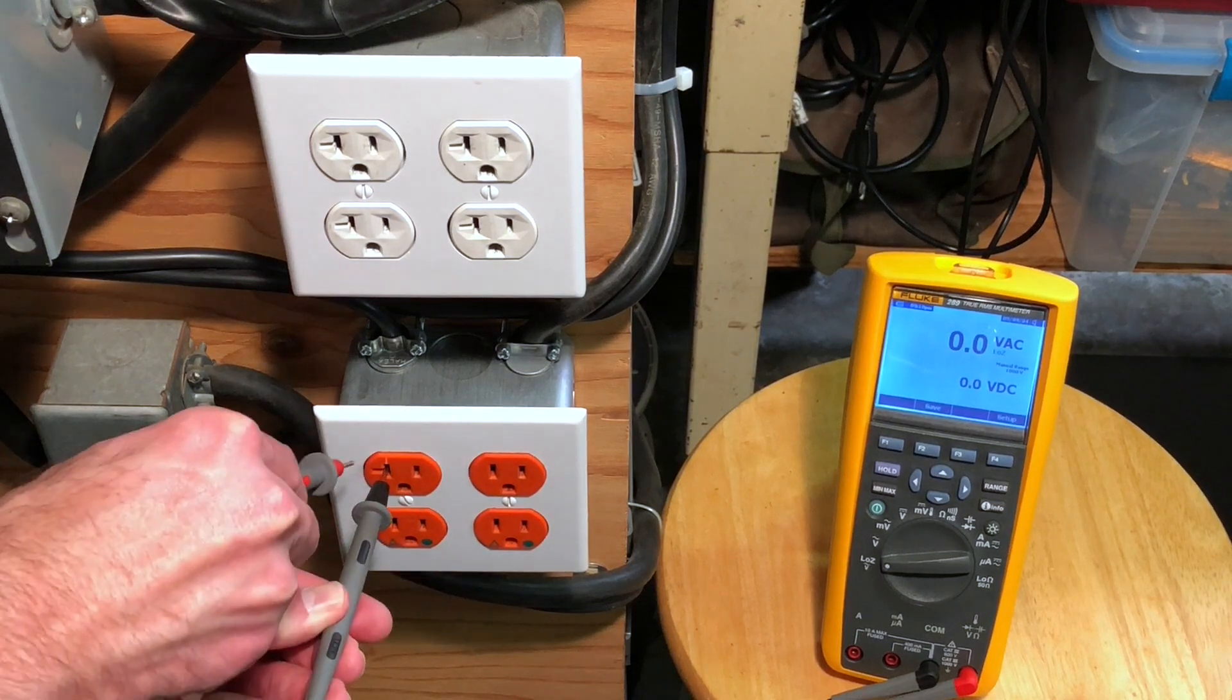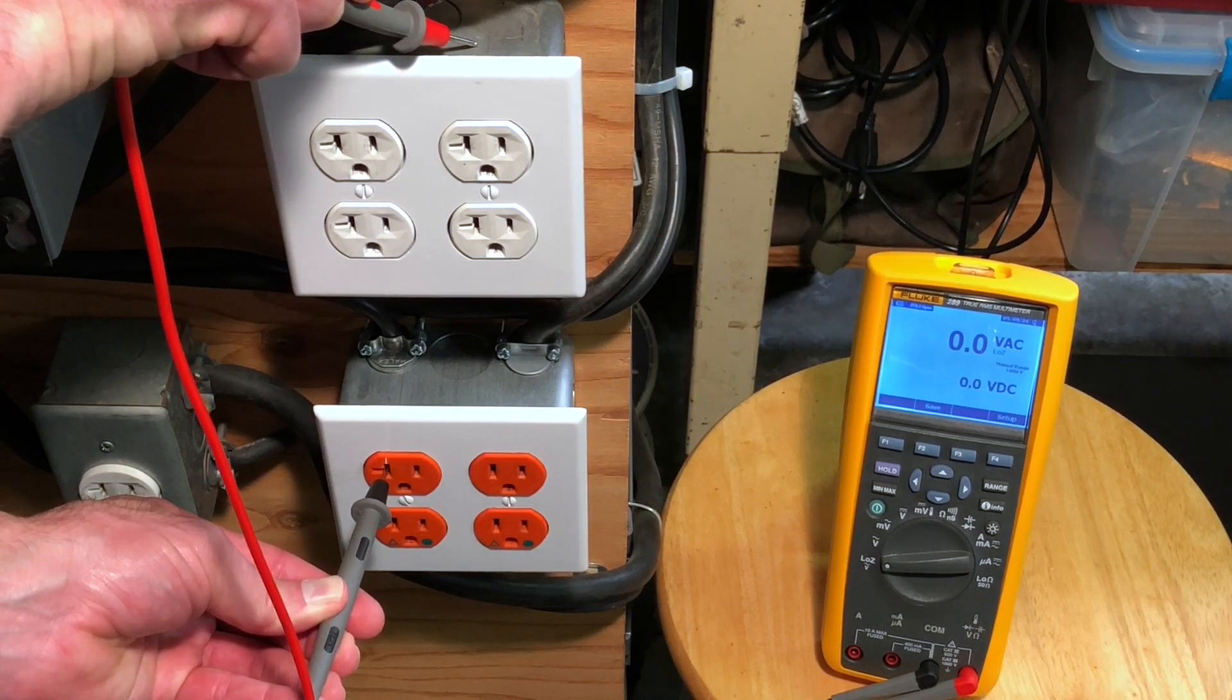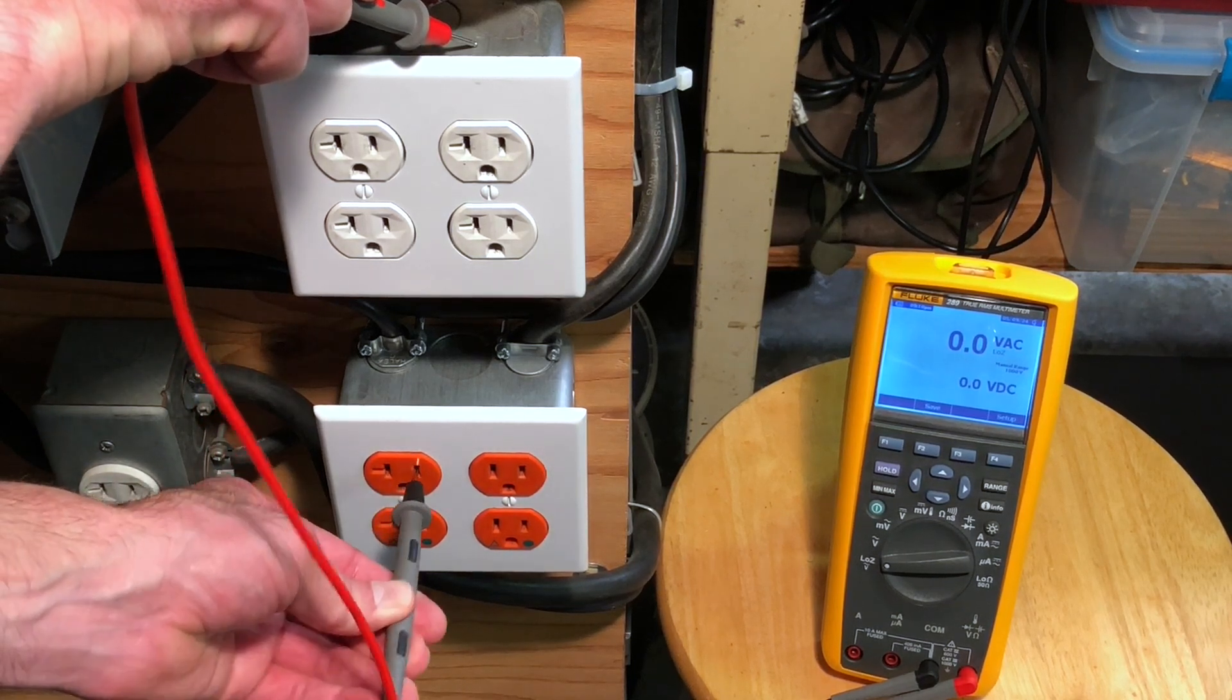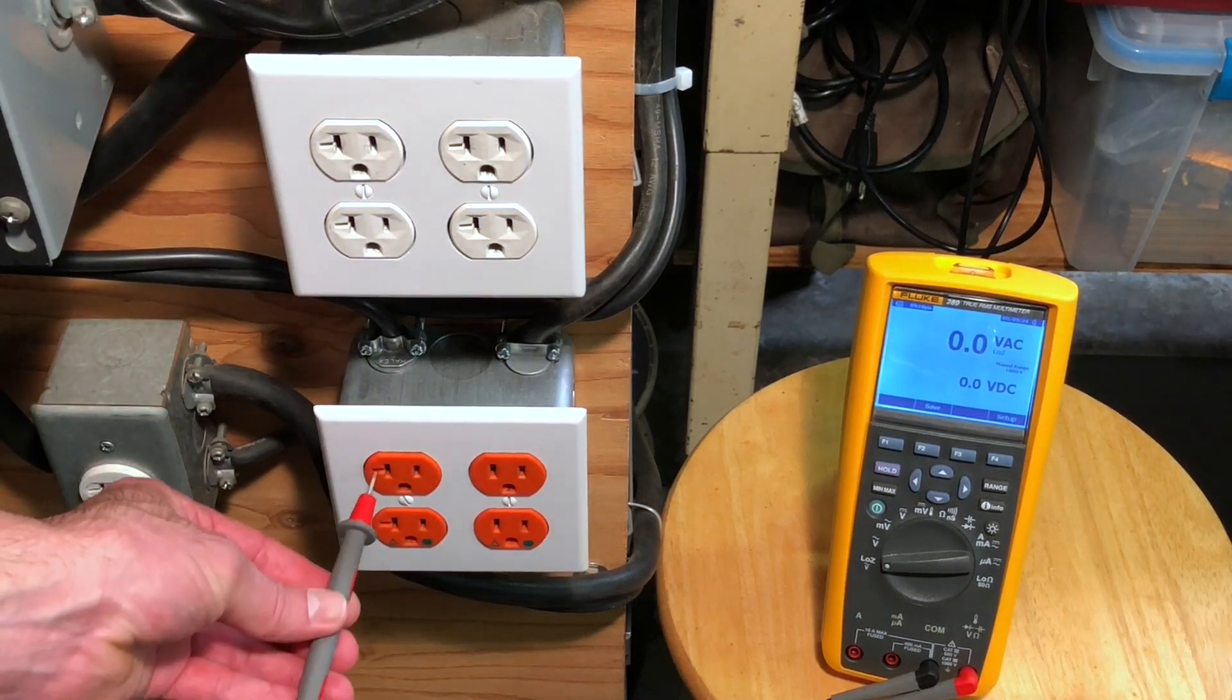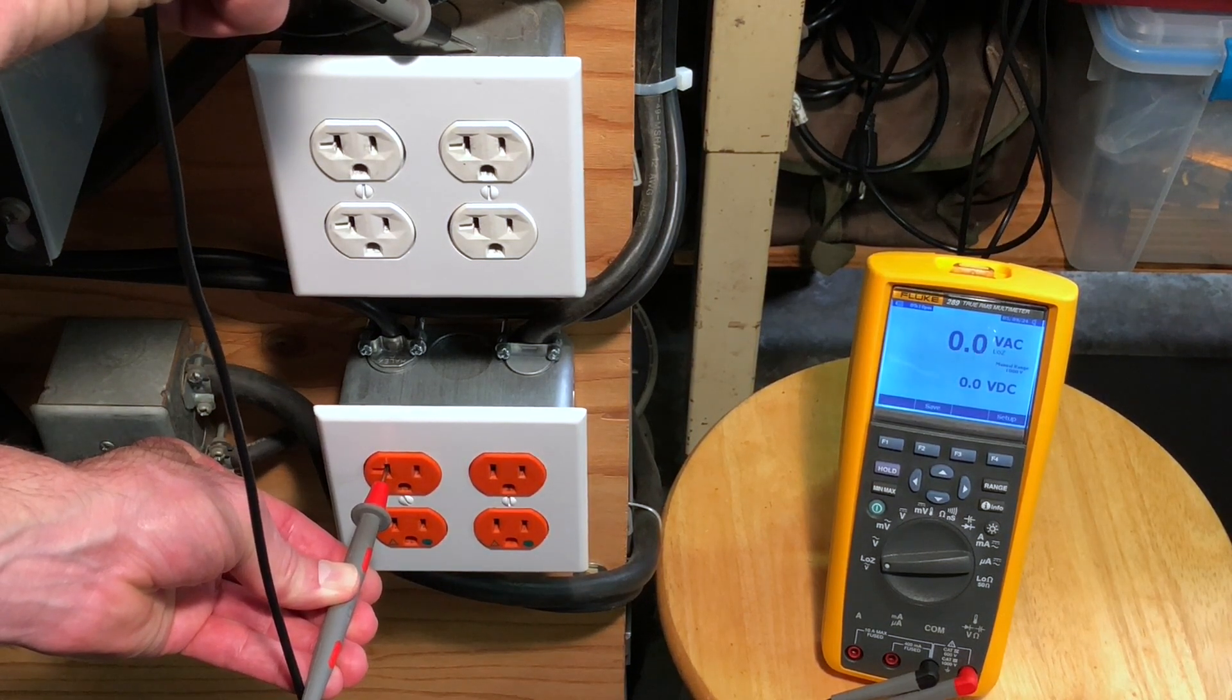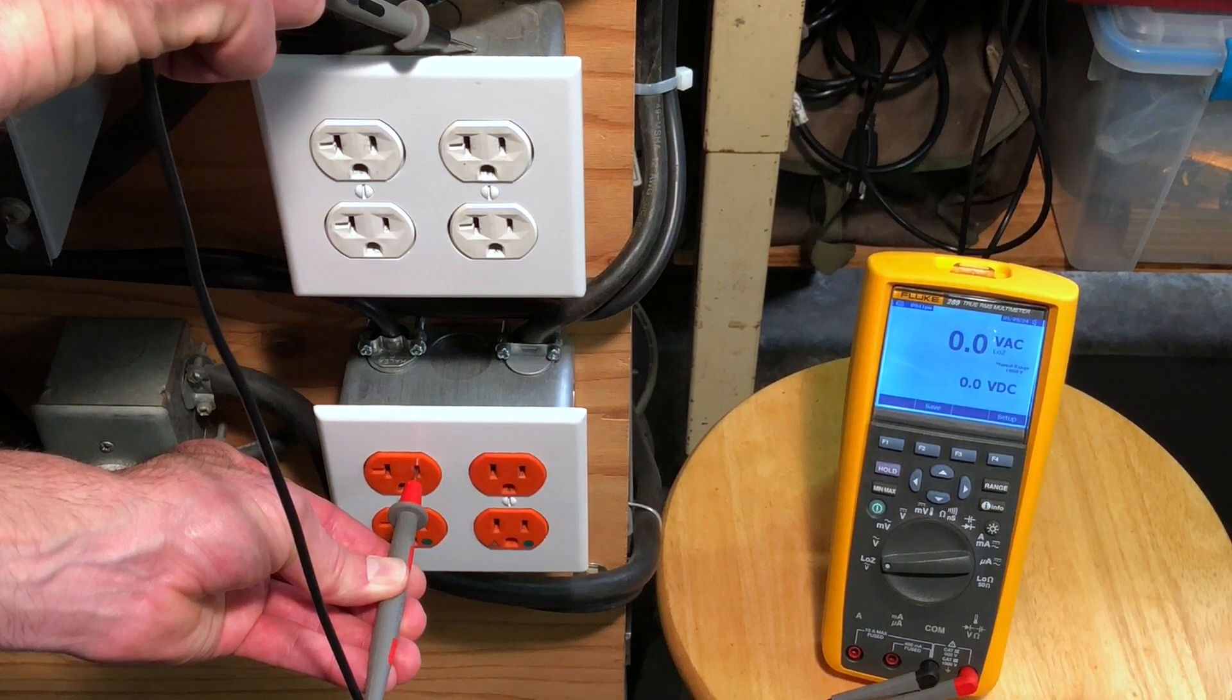Now, if we go to the neutral side and go over to earth ground, nothing, absolutely nothing. Notice the top line, zero volts. If I move this over to the other side, zero volts. It doesn't matter if I reverse the test leads, like so, a tenth of a volt fluctuates, now it's at zero. Go over to the other side, zero volts.